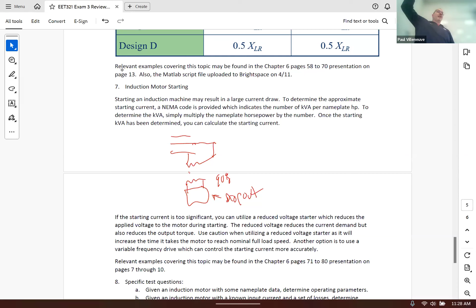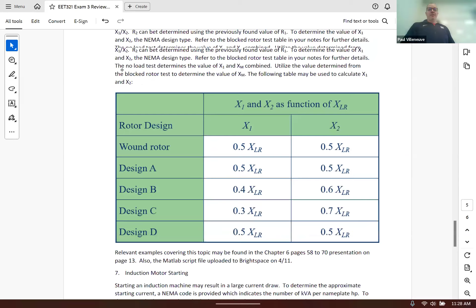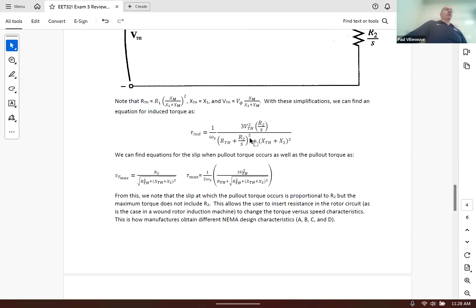If you can start the motor up at 85%, that's going to take less time. But be mindful, as you keep adjusting those voltages, the torque available is directly proportional to the square of the voltage. So if I drop that voltage by 0.65, that's 0.65 squared, so now you're talking 0.3, 0.4. Now you've really got way less torque, so it's possible that whatever mechanical load you have might not be able to spin because the voltage is so small. That's why they give you some additional options there.